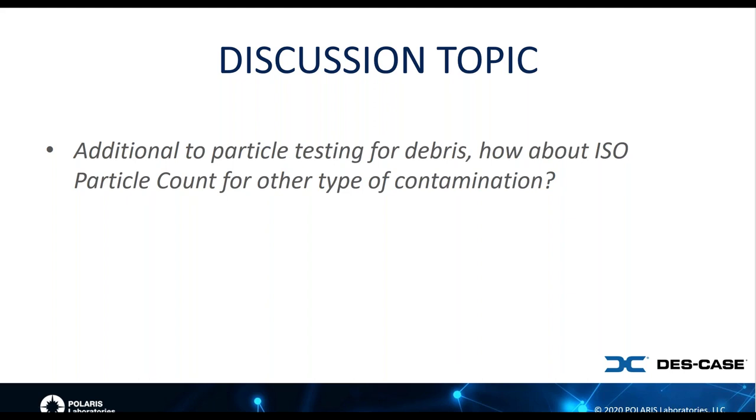Yeah, so I want to say it's been about 2 years. We went to new particle counting machines and a new method that has really helped small amounts of water basically be neutralized to still give you an accurate particle count. Now, I will say, even with that, it does have its limits. If you're looking at a massive water ingression on a mineral oil, it's still going to cause enough problems that it will skew those results.